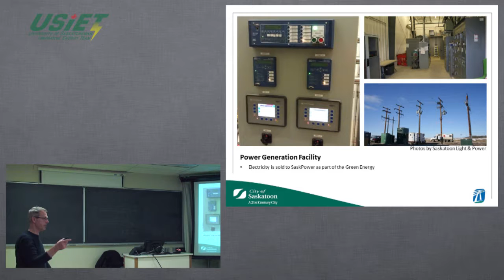gas. And we have to synchronize to SaskPower's grid. So these are the protection relays and synchronizers that do that. And then this is our interconnection to SaskPower at that facility. So we generate power at 600 volts, and we transform it up to 25 kV, and then supply it to SaskPower. So we're also doing a solar photovoltaic demonstration project at the site.